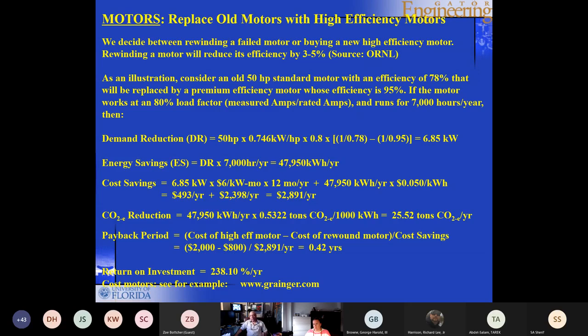And that will translate into, you multiply that by $6 per kilowatt, correct? So you're going to have that savings. And then the energy savings are going to be the demand reduction multiplied by the number of hours that you ran the motors, which is going to be 7,000 hours per year. You end up with 47,950 kilowatt hours per year of savings. And then you add the two together. You're going to take the demand savings, which is 6.85 times $6 times 12 months, plus the 47,950 multiplied by the cost of electricity, which is 5 cents per kilowatt hour.